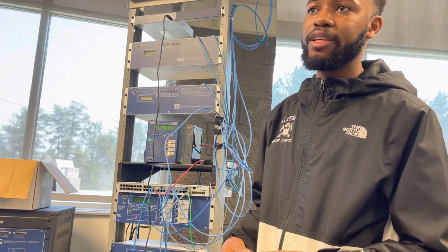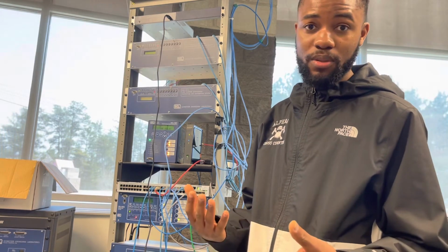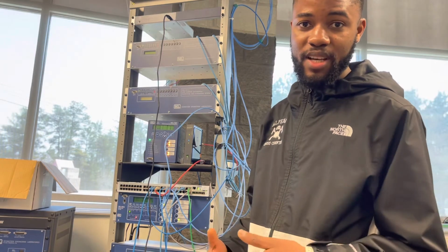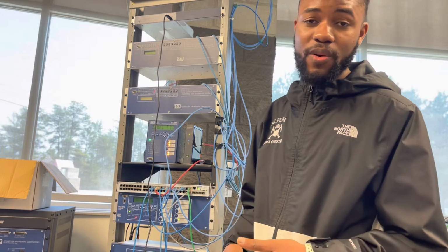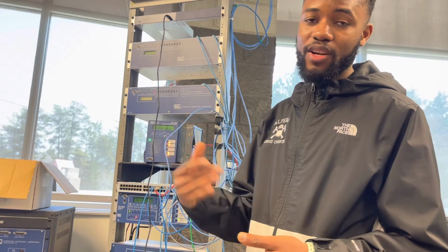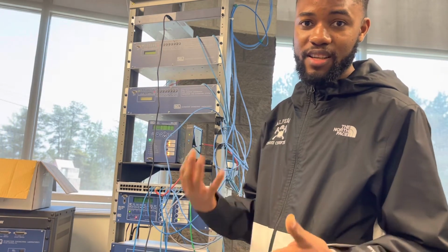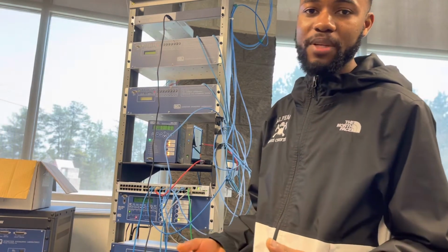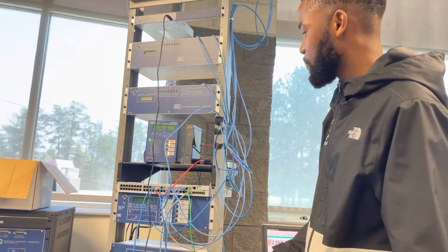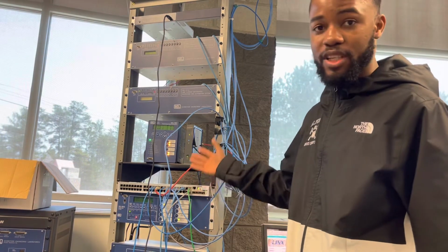And also you can open and close and trip, and you can actually put a fault on the line and see how much the fault current is going to be. And you can also go into the software and see the waveform and the timing, the timestamp of what happened, what's the event file. So these are just the hardware and the communication setup.